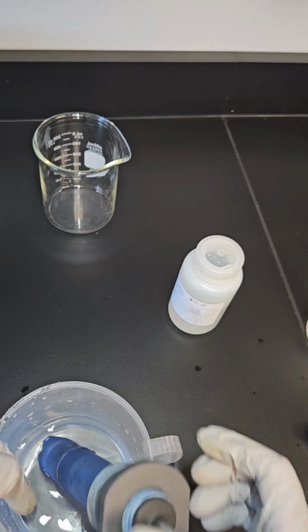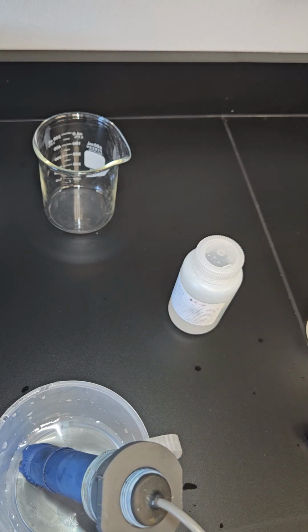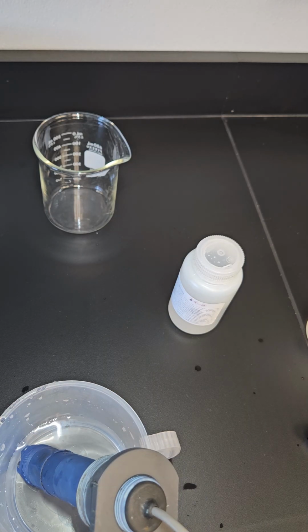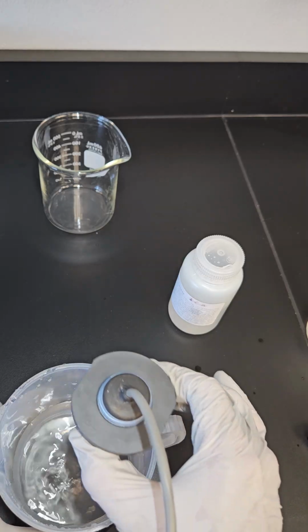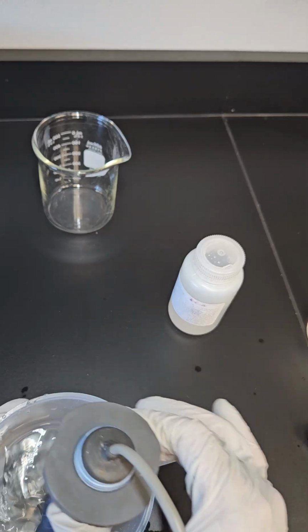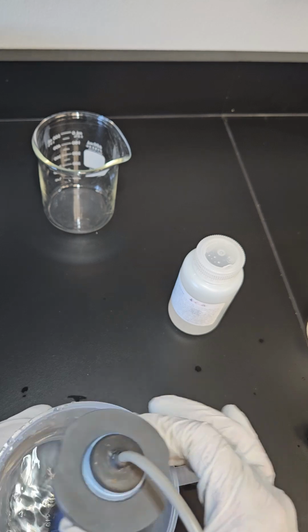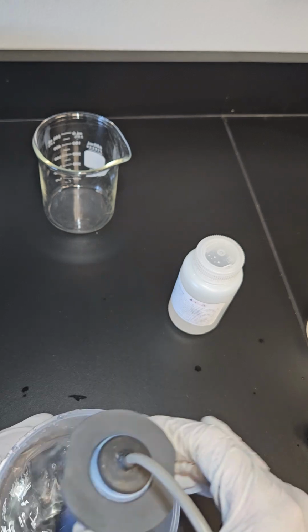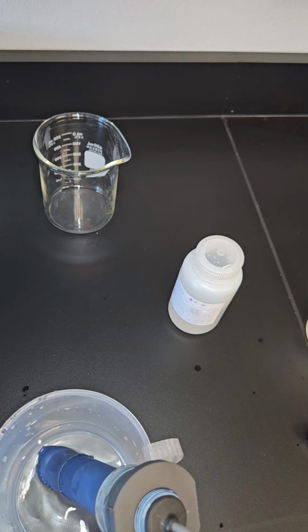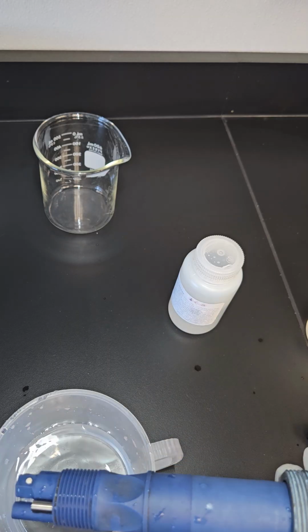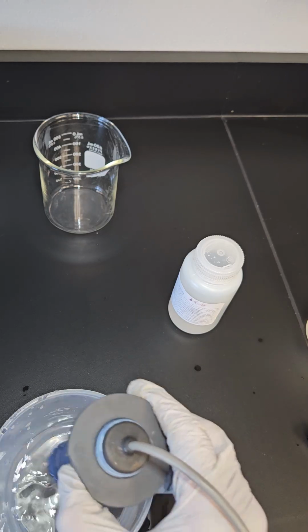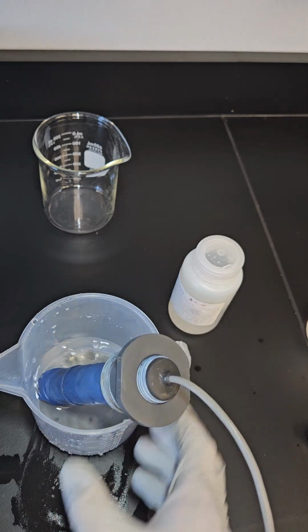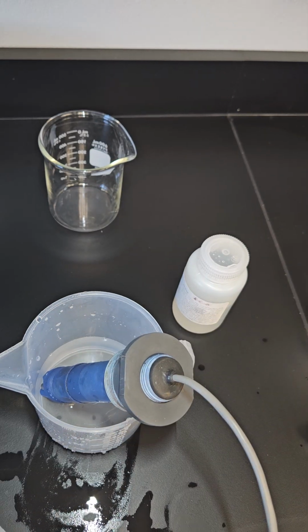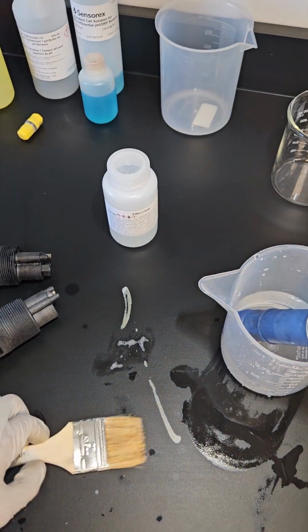You can even take pH paper and test the water, see if you're getting most of the acid out of the probe, because it won't come out right with just one simple rinse. And you definitely don't want to have this probe fail calibration because there's leftover acid in the salt bridge on the surfaces and stuff like that. So a good thorough rinsing after an acid clean is necessary. Once it's been thoroughly cleaned with acid, then you can go ahead and calibrate if you're not replacing the salt bridge solution, or the salt bridge and the salt bridge solution. If you're replacing the salt bridge and the salt bridge solution, then we go one step further, and I'll go to that point next.